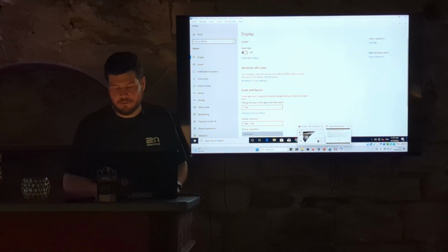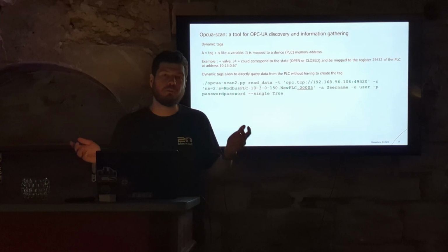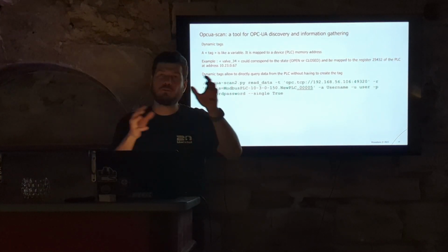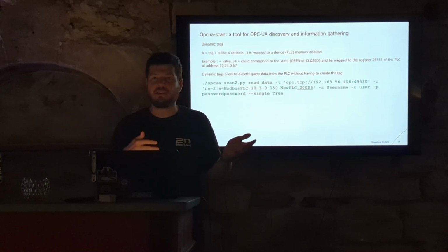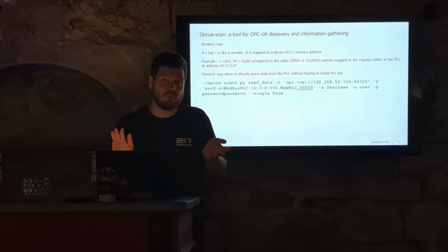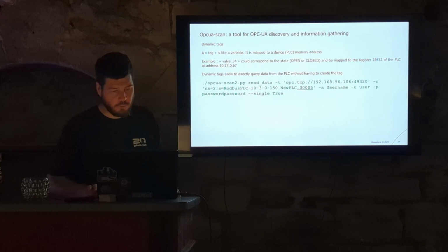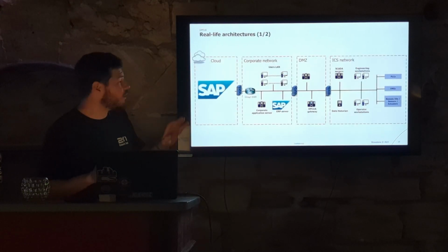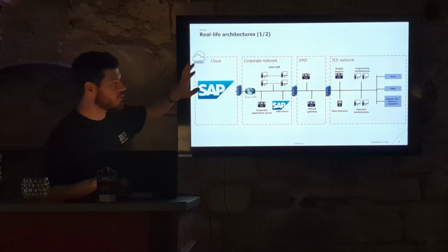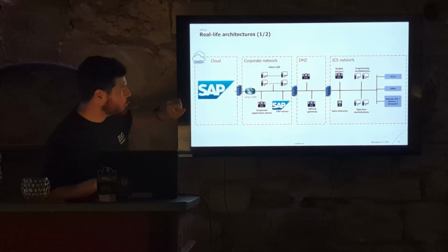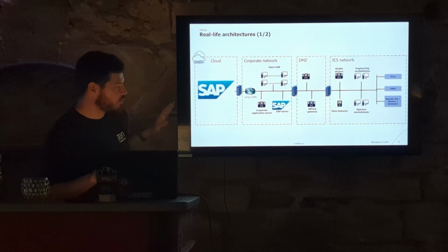those solutions are usually meant to collect some data, and you do not want the people that have the right to collect the data, process it, to do some data analysis. You do not want them, most of the time, to be able to write directly to the memory of the PLC. Okay? In terms of architecture, and that's the last slide, what I assessed was something like that. So it was quite secure.